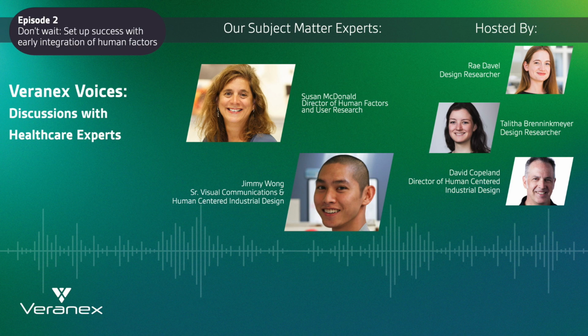I agree, Jimmy. One thing I should touch on too is that the FDA does not want to see a usability validation where no users were ever brought in to try the device. If you think you're going to not study for the test and come in at the end and take this test, it's not going to go great. You might learn things about usability that are much more expensive to go back and fix, but also you are not showing that you've done your due diligence to make sure you're meeting the needs of the user. So they really want that full story.